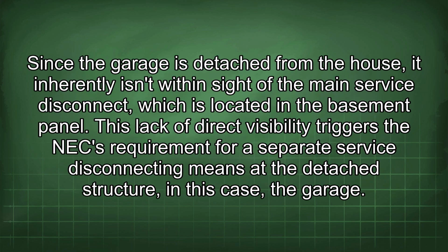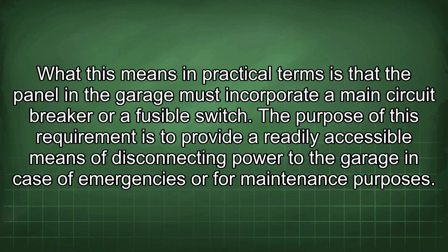Since the garage is detached from the house, it inherently isn't within sight of the main service disconnect, which is located in the basement panel. This lack of direct visibility triggers the NEC requirement for a separate service disconnecting means at the detached structure, in this case, the garage. What this means in practical terms is that the panel in the garage must incorporate a main circuit breaker or a fusible switch.